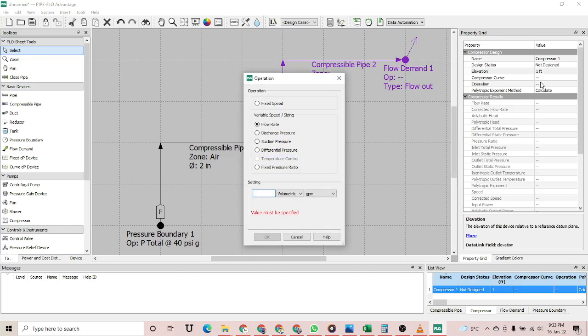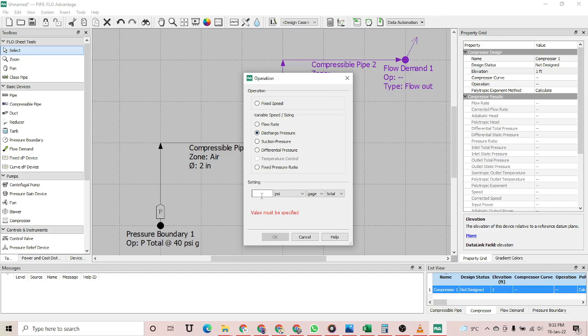For the compressor operation, you can size it based on different available specifications: you can specify flow rate, fixed speed, discharge pressure, suction pressure, differential pressure, or fixed pressure. I am going to select discharge pressure, and I am specifying that this compressor should be able to discharge the fluid at 88 psig.